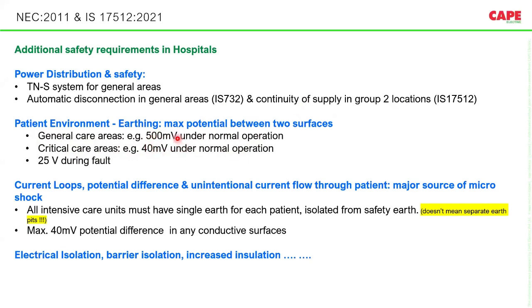So the supplementary equipotential bonding must be very, very efficient to reduce the potential difference lesser than these. You see, 40 millivolt is a negligible voltage, but more than 40 millivolt itself sometimes is deadly for a patient. And during fault condition, the potential difference must be limited to less than 25 volt. So very important: supplementary protective equipotential bonding.